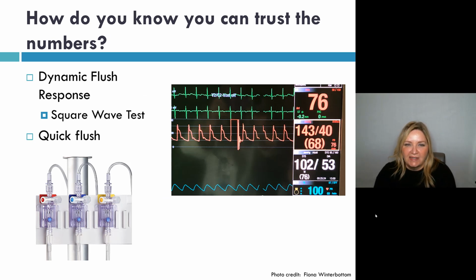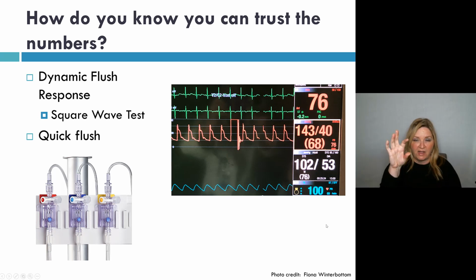The test that we do is called a dynamic flush response, or dynamics. You might also hear it called a square wave test, but these are all the same. So basically, with your transducer, I've got an ART, CVP, and PA line here, but just focus on the ART line. You're going to either squeeze and fast flush, or some of them might have a little pulley system on it, and you do a super quick, like 1 second, fast flush. And what you'll see is the value will go up.